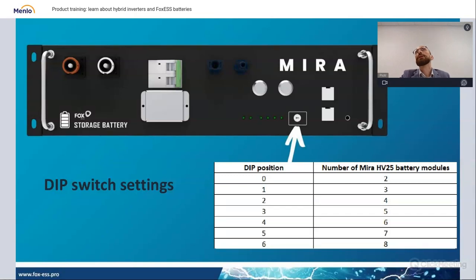We have 2 communication terminals, 1 for the inverter, 1 for the first battery in the stack. Those connectors are RJ45. It's a standard Ethernet cable, so you can also provide your own cables if those provided with the devices are too short. Of course, we provide power cables for the inverter and the BMS, and also battery connections. Battery cables are also in the set. We have also added communication cables for every battery, ready to be connected to the stack. And earth cabling is also in the packet, to properly and quickly ground those batteries.